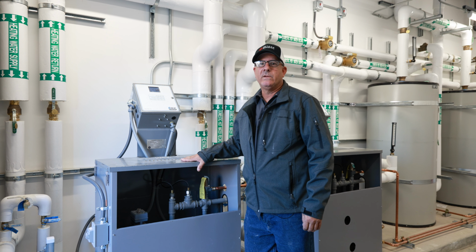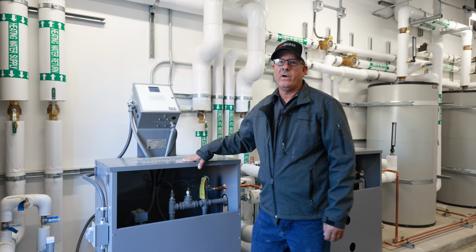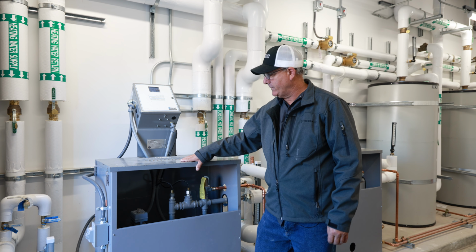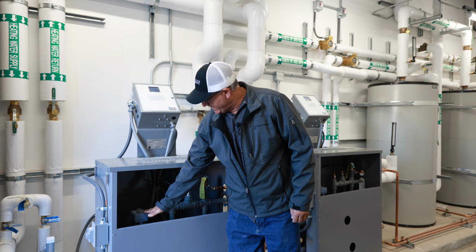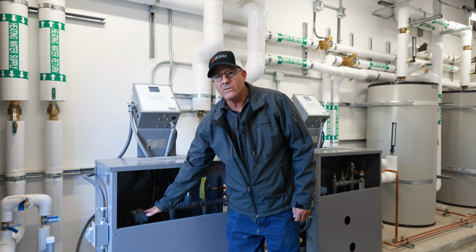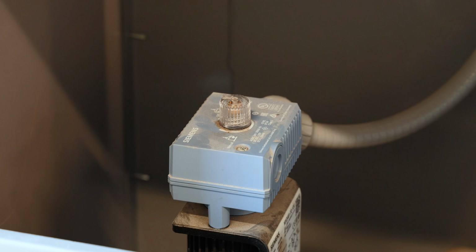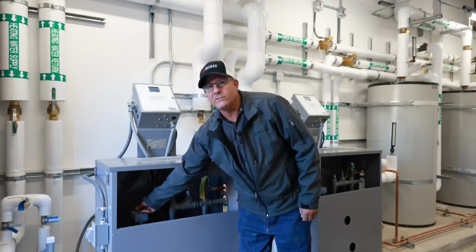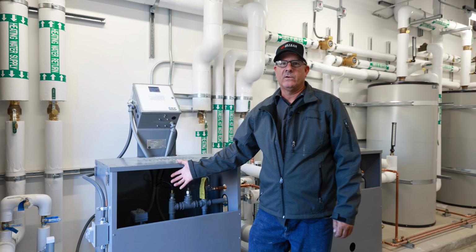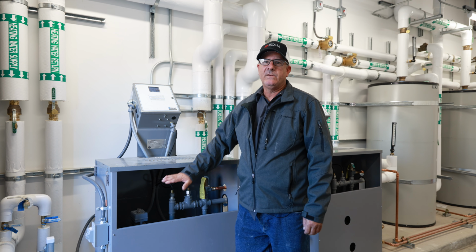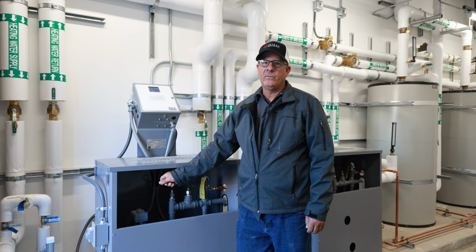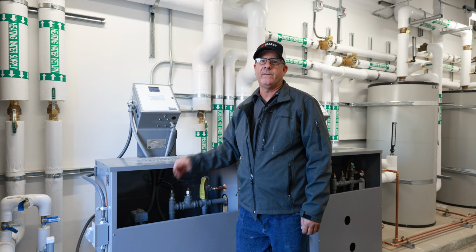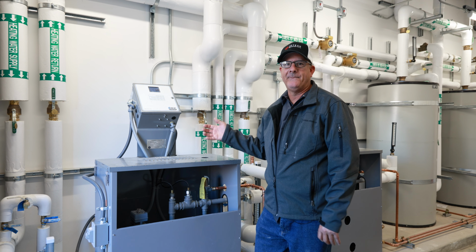Okay, so we're back at one of the heat exchangers for the domestic hot water. I wanted to touch on a couple points here. Below me is a manual water flow valve. In case the temperature controller fails, you can manually depress this knob, turn it to the right, and you will have hot water going through the exchanger. Make note on this, you've now put it in manual mode, so you'll have to monitor the water temperature in the tank so it doesn't get too hot.